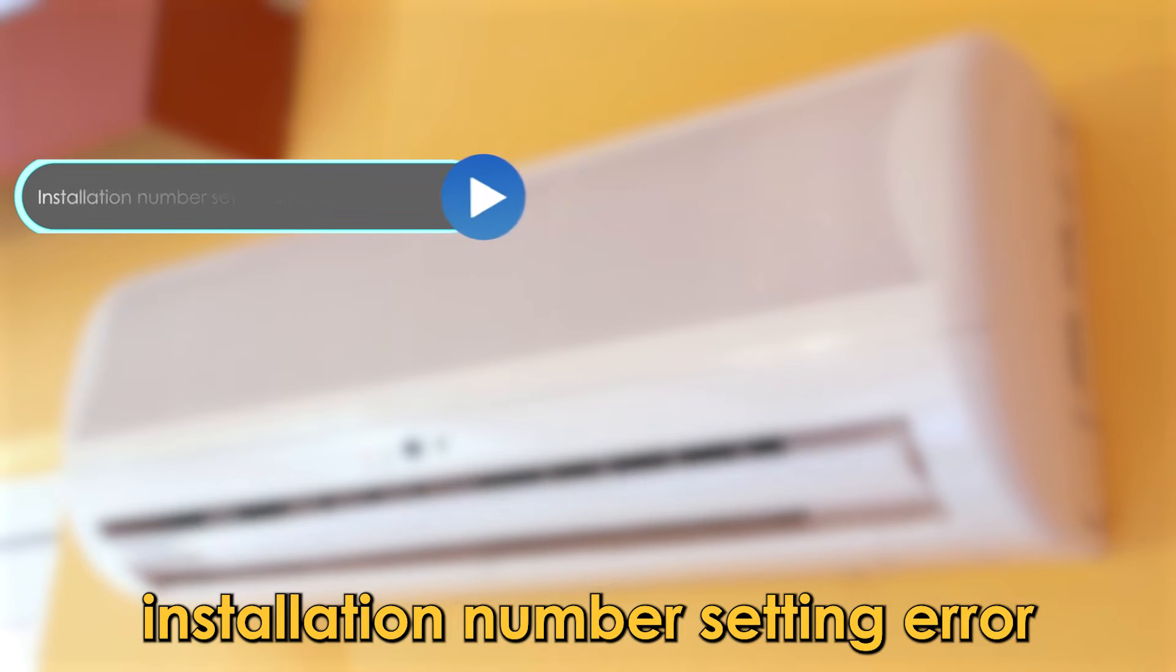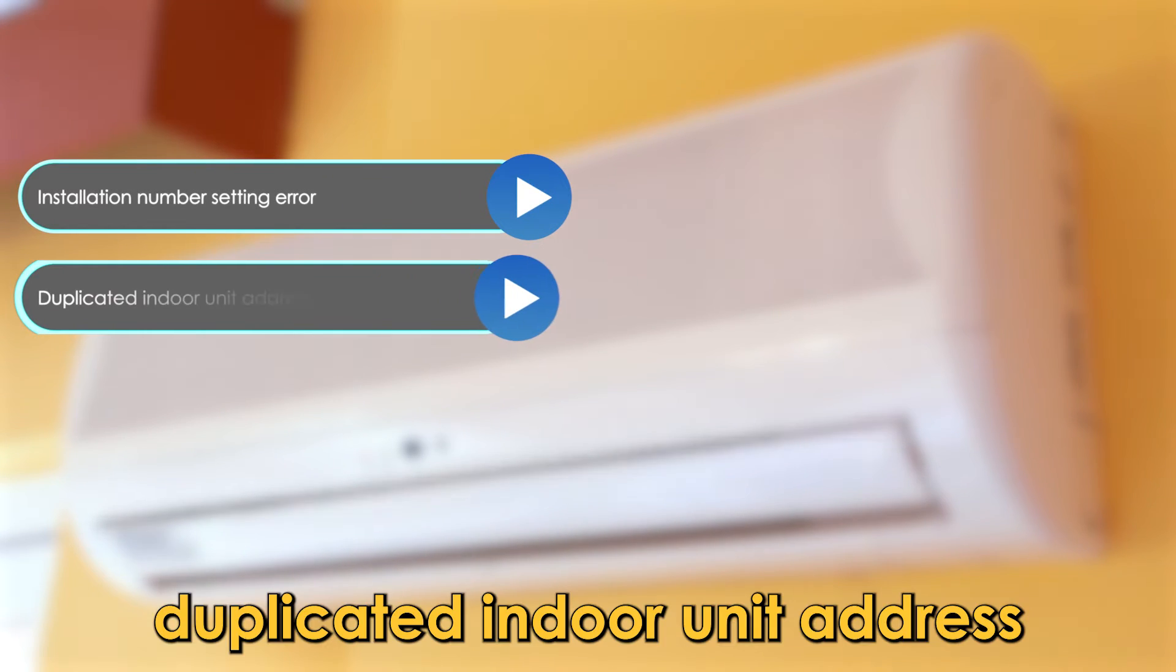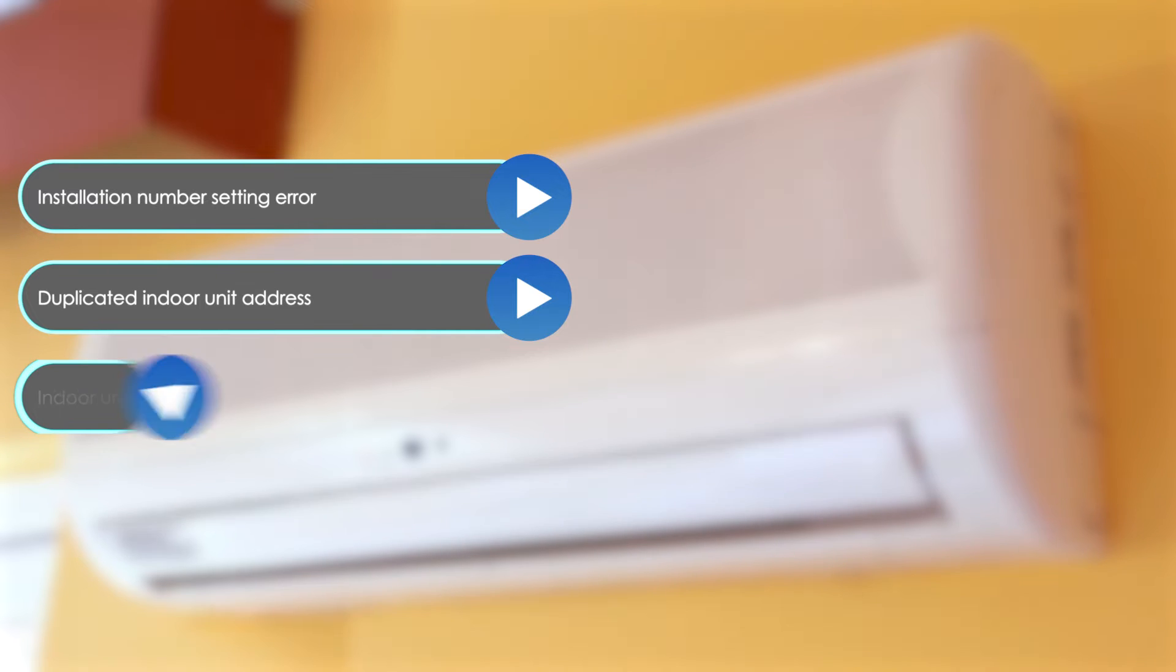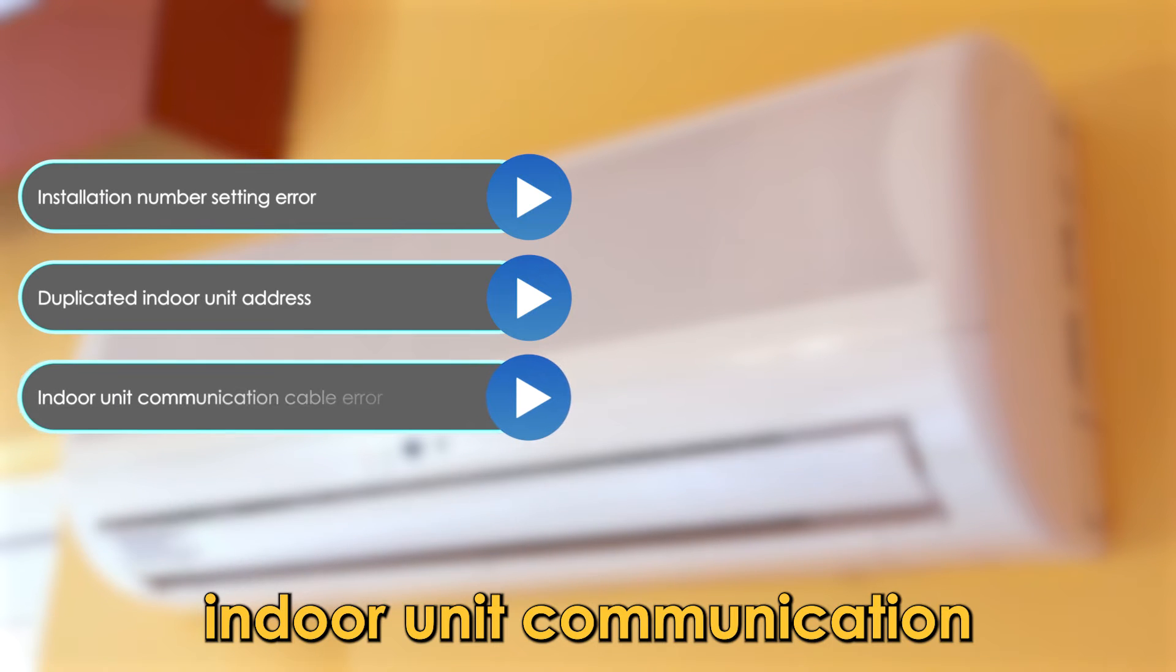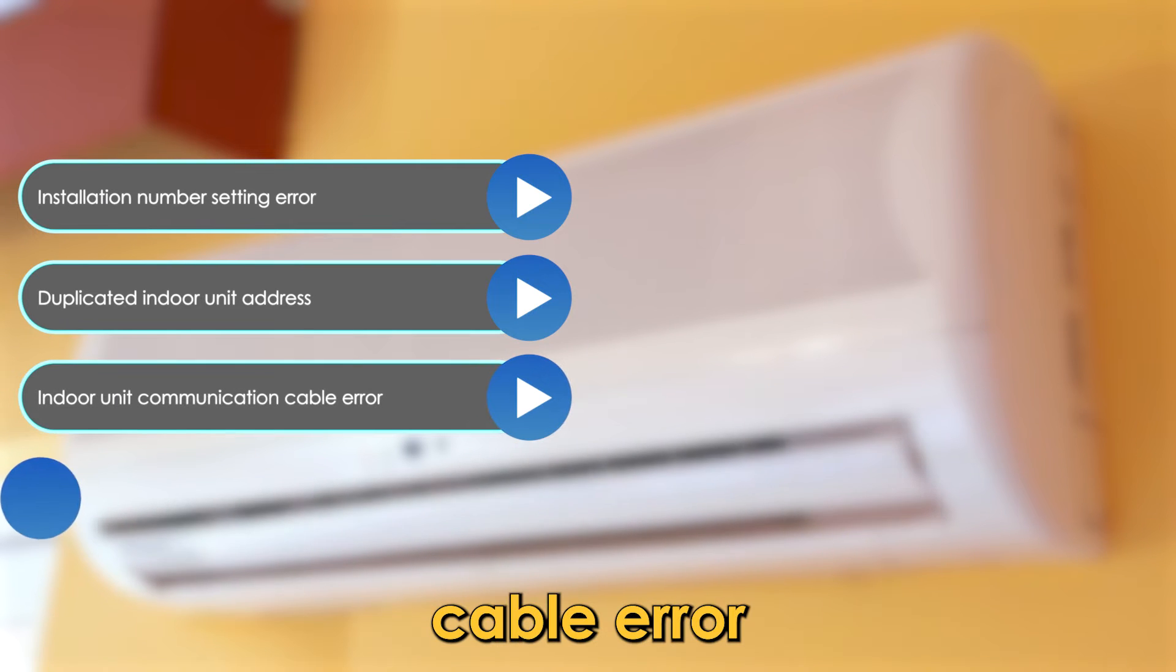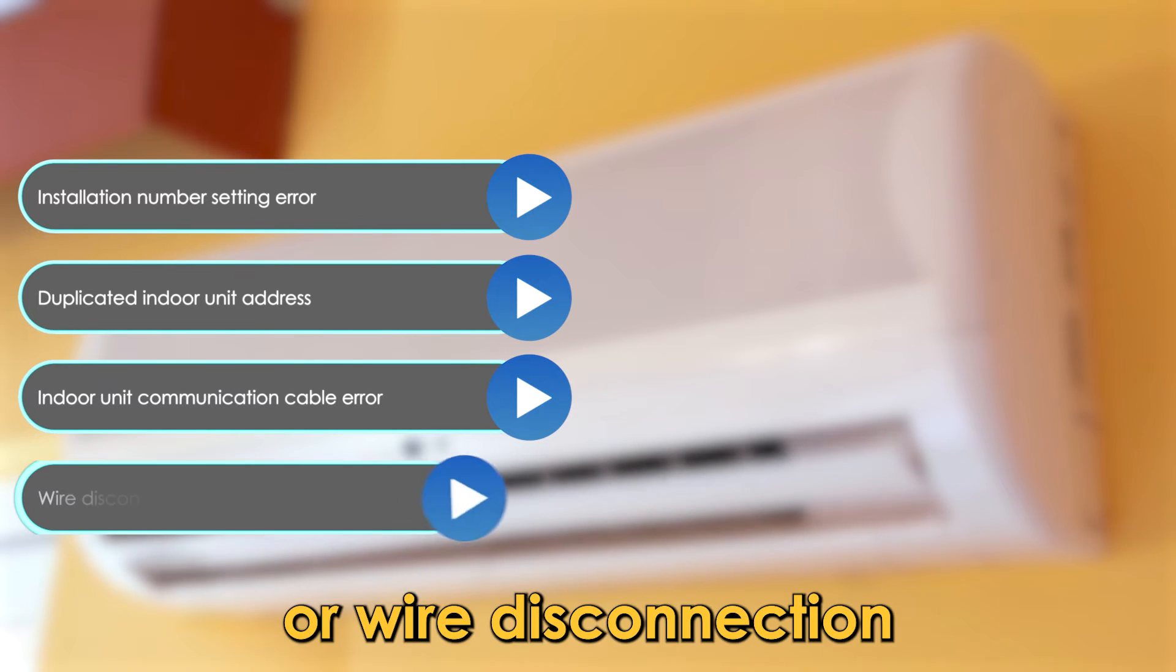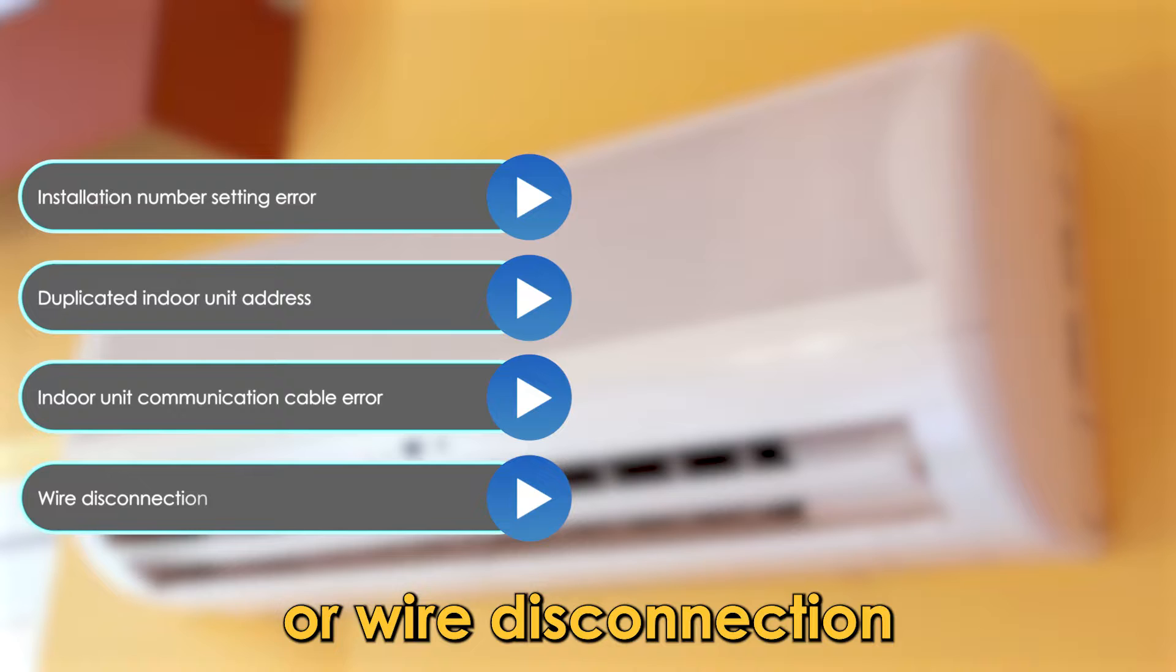The following are some causes of this error: installation number setting error, duplicated indoor unit address, indoor unit communication cable error, or wire disconnection.